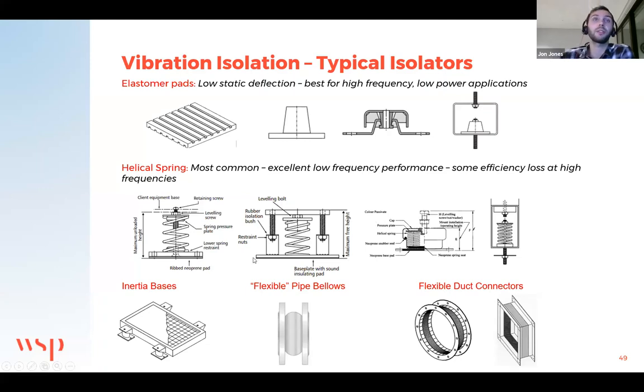To improve that further, on some equipment you can mount it on an inertia base, particularly pumps. Inertia bases have the benefit of adding a lot of mass, which ties in with my last point about loading the springs to a certain point. It helps compress the springs and improve the isolation efficiency. It also has the benefit of lowering the center of gravity of a moving piece of equipment. So the forces that are then transferred into the structure are reduced.